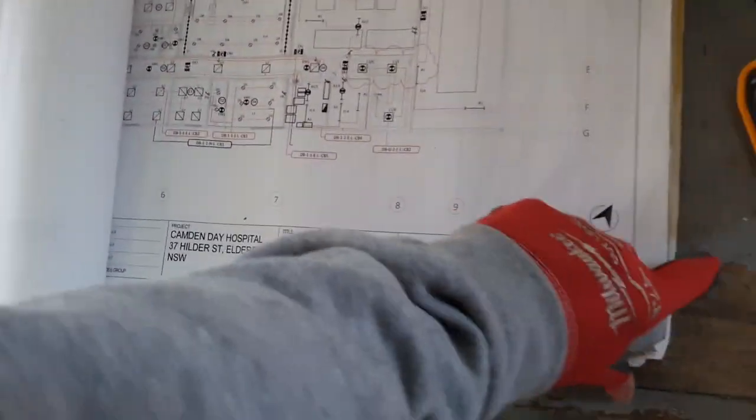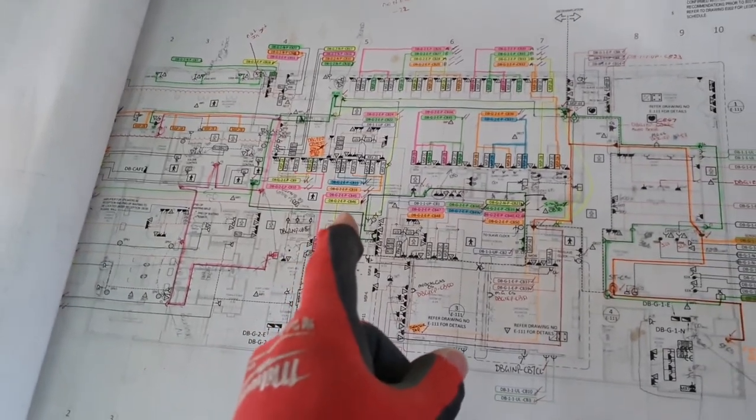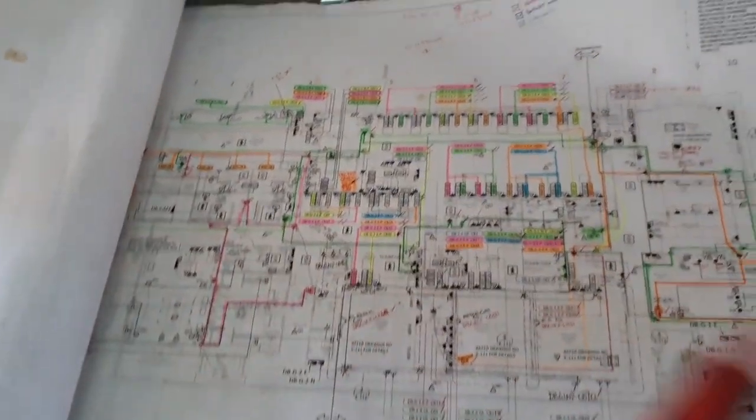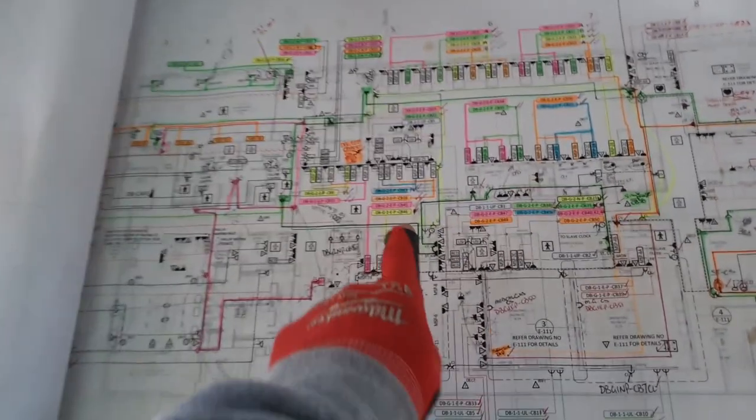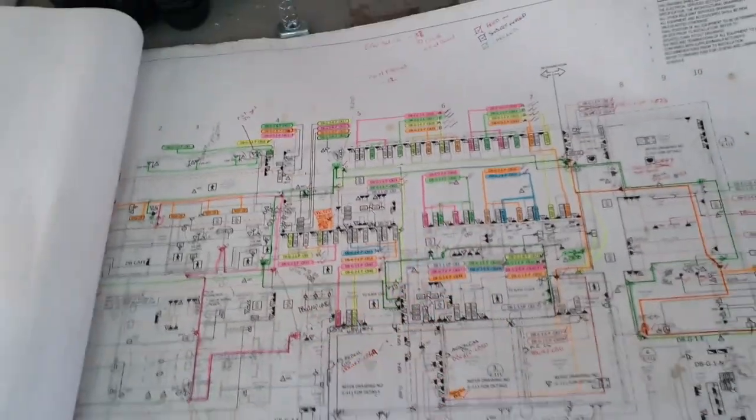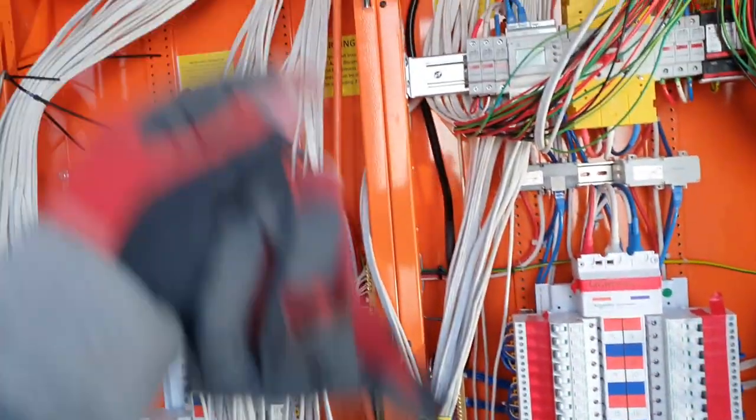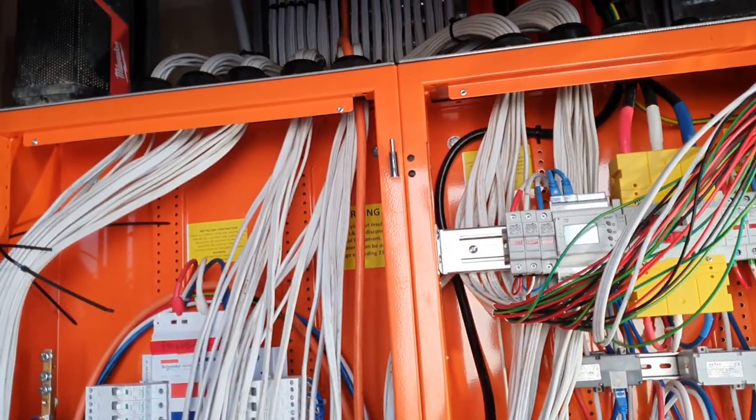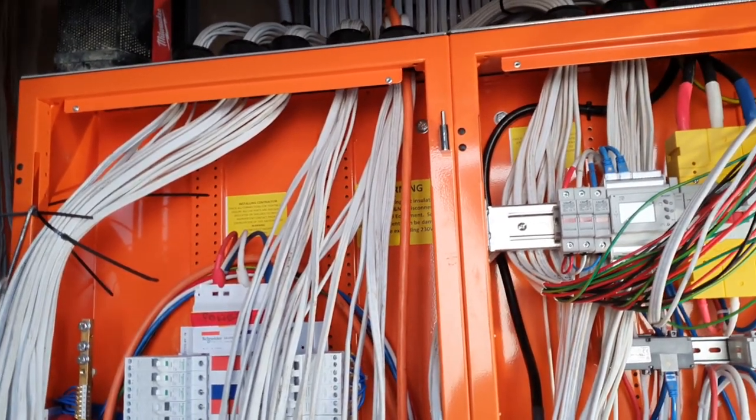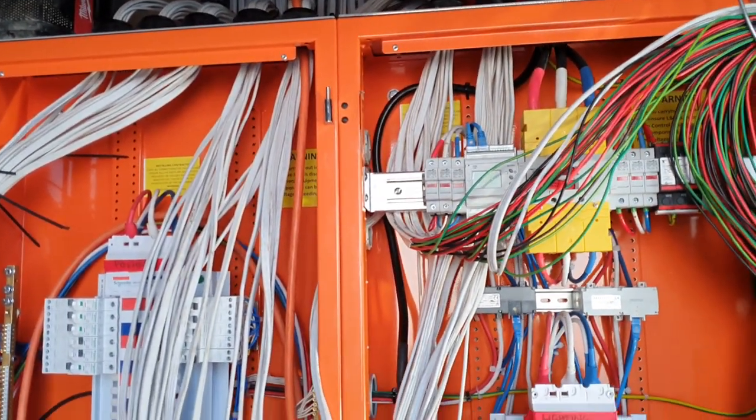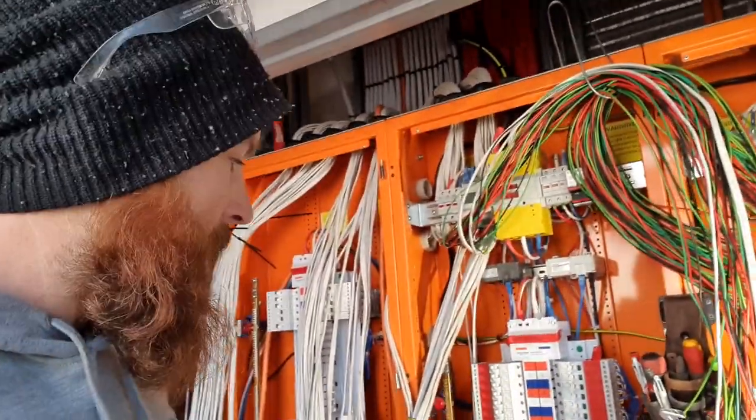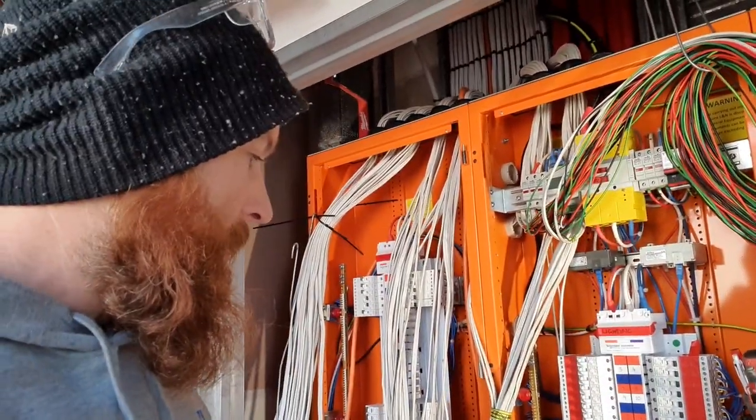And that's probably where I'll pick up with this video next. But I'm stripping and marking my circuits. This is my method for doing a board like this. You definitely want to mark up what you've got, if it's there or not. I've got the emergency circuits there as well. And then on this side with the power, I'll start doing that once I've started stripping and relabeling it with my little method. Then tick them off on the plan. After this, I've got to go over here to my actual drawing and click along to the power section, well lighting section, and just confirm that I've got everything. Because you need to double check before terminating. With the way that I terminate switchboards, I like doing it very neatly. I don't want to come in and say, oh fuck, we've missed that circuit or it's hanging out in this bundle or something. I want to make sure that every single circuit that I've run in the building, that's highlighted off as ran, I want to make sure it's in that board before I start terminating. So that's my little pro tip. When you've got close to over 50 circuits here, you definitely want to make sure that everything's there before you start.